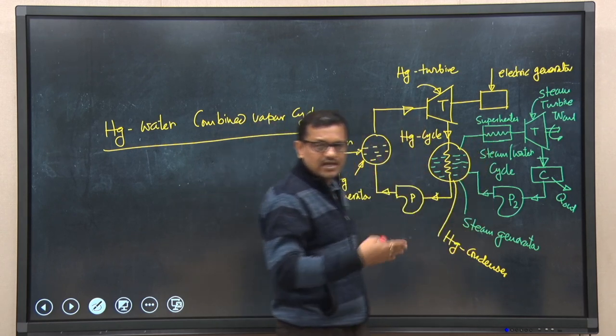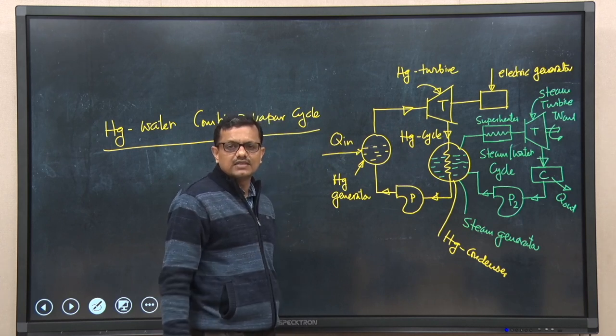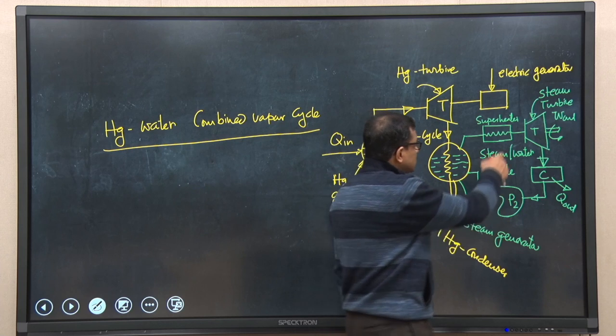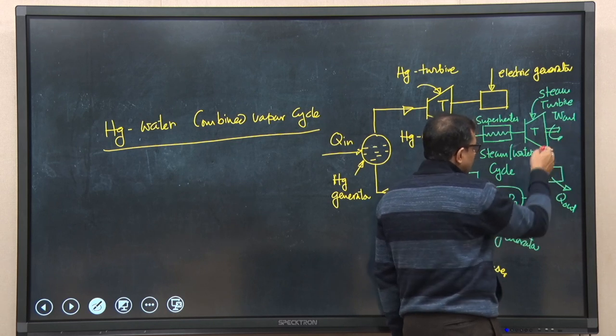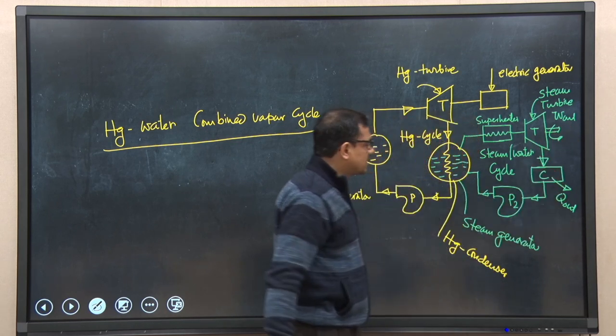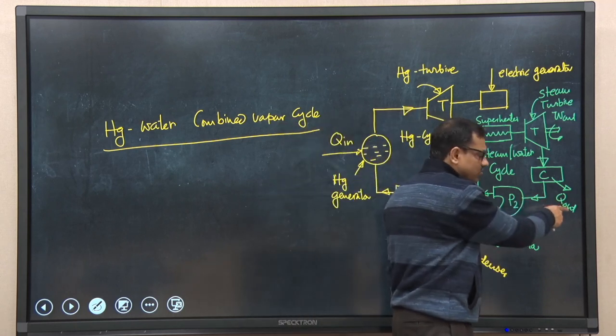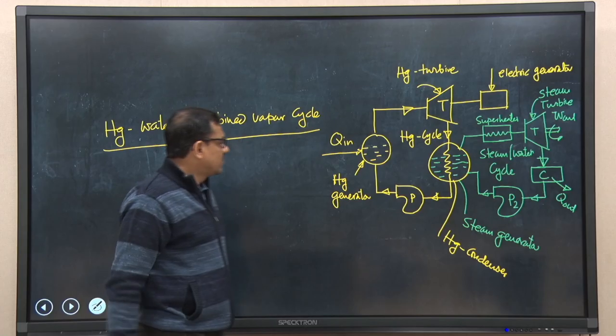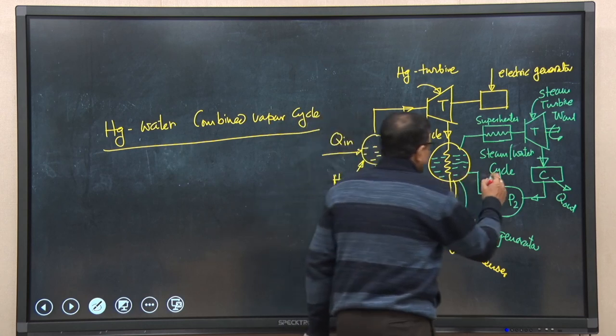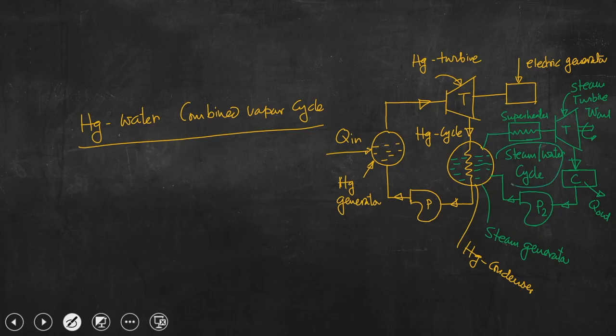Whatever steam is generated in the steam generator is in contact with the water, so essentially the steam obtained is saturated steam. To increase the quality of steam we need to superheat it, and that is why it is passed through the superheater. That superheated steam is taken to the steam turbine, does work, and we get W_out.